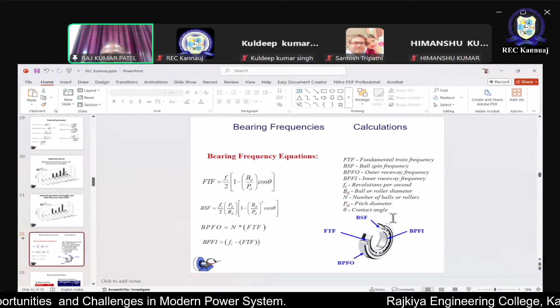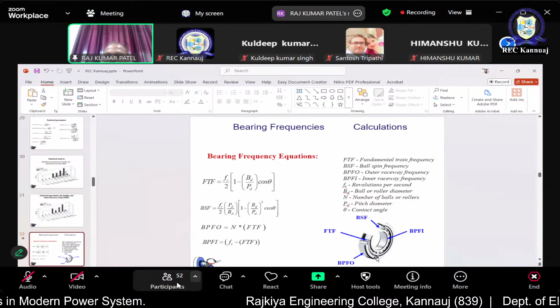Now again we can see the structure of the bearing: the inner race, outer race, ball spin frequency, and the cage FTF. Each section of the bearing will indicate a particular frequency. If a fault exists in the inner race, it will generate some specific frequency, shown as spikes.